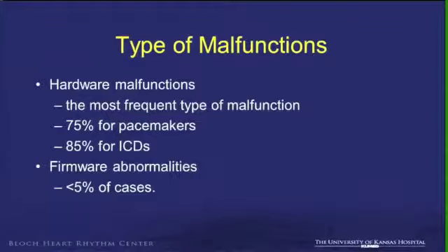If you go by classifying the malfunctions, there are hardware malfunctions and firmware abnormalities. Most of them are hardware. This is lead design, this is generator design. The firmware abnormalities are easier to fix, and they're not as common.